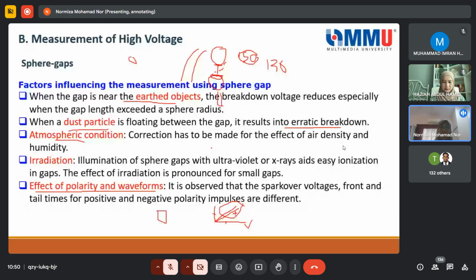That's general, but of course, through my experience, there are certain times that it gives similar characteristics, positive and negative. There are many other possibilities, or statistical characteristics of the dielectric material as well. But anyway, we should know that the sphere gap gives the effect of polarity. It is observed that the spark over voltages, front and tail time for negative and positive are different. So when you test the sphere gap under positive, you will find that the result of negative can be different, even though you supply the voltage from the impulse generator or from the AC or DC source are the same.